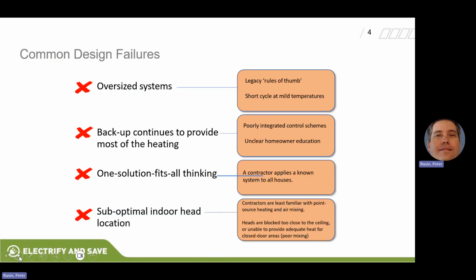Common design failures that we typically see: oversized systems, the legacy rule of thumb where you put your thumb up and that sounds about a 5-ton system. We don't want to do that, where you oversize it and start short cycling at outdoor temperatures.